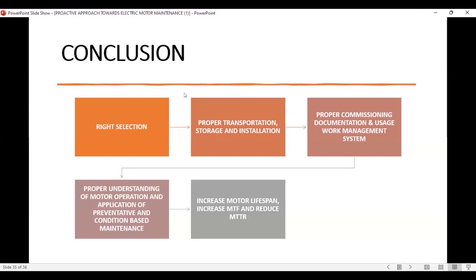Then proper transportation, storage, and installation. Transportation is very important. When transporting a motor, make sure the right things are put in place: the shaft is locked and the motor is properly covered. And when installing, make sure you handle the motor properly. Don't put stress on the bearing, as the motor starts failing even before you run it. And proper commissioning and documentation, and the usage of a work management system. Do proper commissioning. You document all the issues from commissioning, the running current, the motor parameters, the type of coupling, the alignment results, the vibration results. You keep it as your reference point, so during troubleshooting or maintenance, you check it against your baseline.